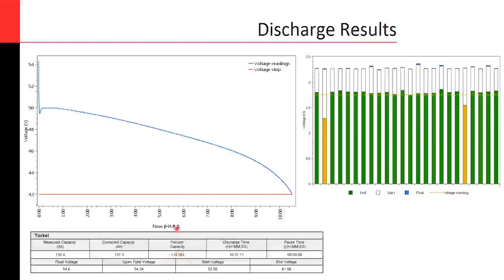This is a combined effort of 24 cells, and as you can see from the other graph, this bar graph of the voltage measurements, there are 2 cells that are not performing that well. If you just perform a discharge test, you might not notice this, especially if you don't measure the voltages throughout the test, and if you don't do any other confirmation test, you're not going to notice a change in the capacity that fast or that easy.